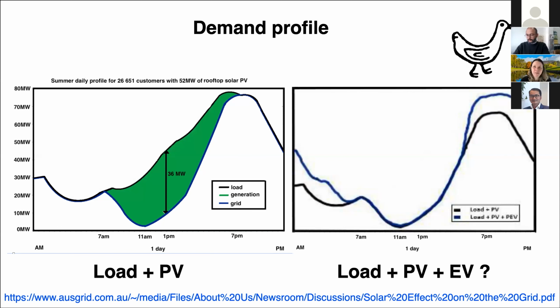There are many ways to expand. Typically we look at expansion because of thermal constraints—the transformer getting too hot, or the conductors sagging too much—and we can resolve that by switching to higher thermal rated capacity. Or we could have voltage constraints, and ways to alleviate those could be tap changing transformers, adding capacitors, or reconductoring as mentioned before. Additionally, tap changing operations or voltage regulation equipment, including new equipment like inverters, can help.